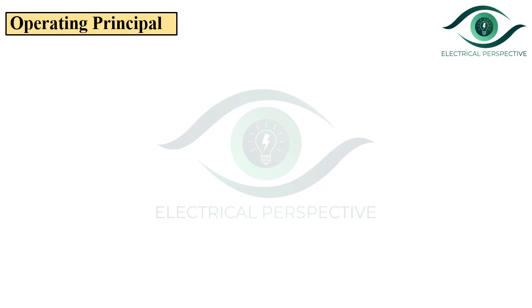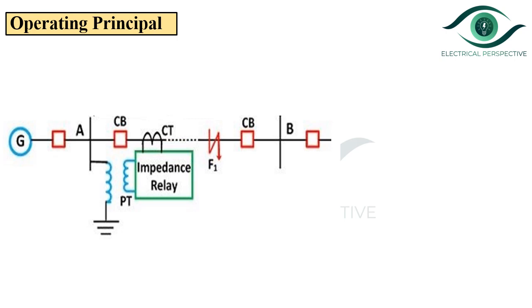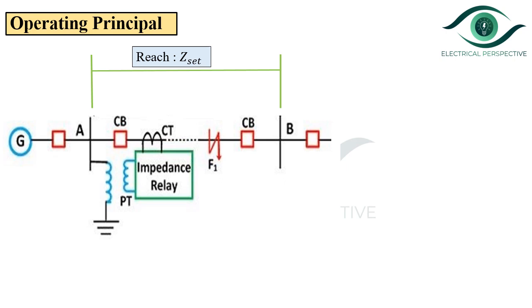Let us see the operating principle. Consider the transmission line AB as shown in the figure. Assume that there is a source only at end A and we wish to generate a zone of protection which extends from A to B. Assume that the impedance relay is located at end A. The impedance relay requires two quantities as input: voltage, taken from a PT (potential transformer), and current, taken from a CT (current transformer). As we wish to extend the protection to section AB, the reach of the distance relay is made equal to Z-set, which is the impedance of section AB under normal operating conditions.